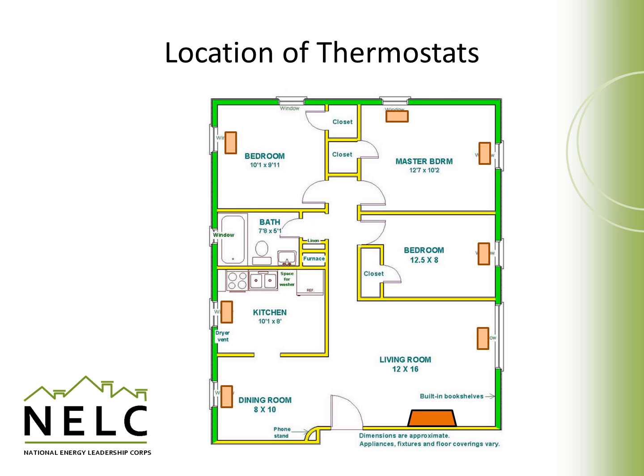perimeter, often around windows to offset the temperature differential that a window can introduce compared to the outside walls. And it would be an important consideration, if you're introducing heating or cooling at these places, that the thermostat shouldn't be placed too close to them or placed next to an odd temperature, for example, a fireplace or a door.